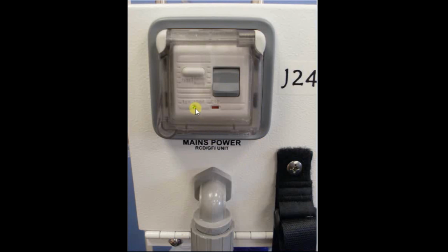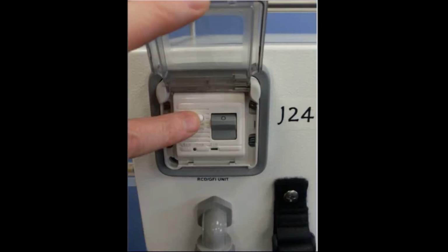As you can see here, there's a little green light indicating that the mains power is applied, and the button up here is depressed and the little 1 is visible just here, indicating that the switch is on. Here it says test, and if you press this little button in normal use, this should trip the switch out, which I've done here. Pressing that button, the little LED has gone out, the switch is tripped off. We now see a 0 up here, indicating that the main supply to the machine is off.